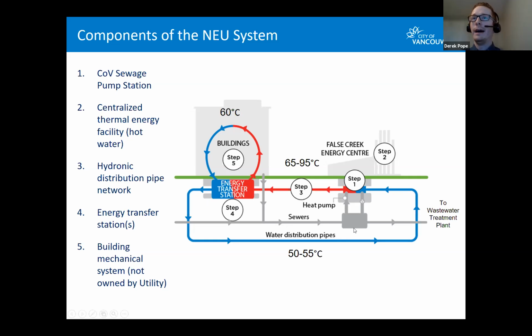We take some of that sewage, bring it into the plant, and harvest some of that waste heat using a heat pump. The heat pump rejects that waste heat into our own closed loop piping system, so we can produce pretty hot water using a heat pump, up to 80 degrees Celsius. We also have gas boilers that we can use to top up the temperatures as needed if we have particularly high system demand.